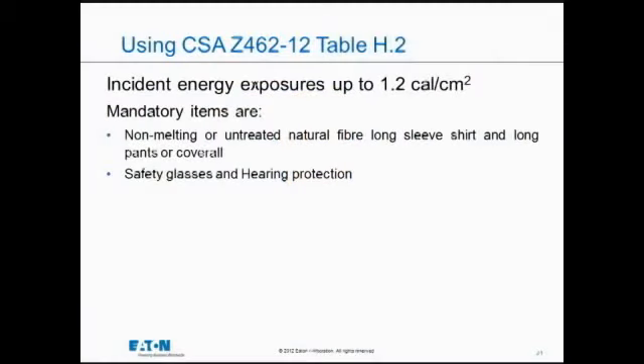They've tested jeans, cotton jeans, 100%. That will ignite somewhere around 2 calories. So there's a fine line between catching on fire and not catching on fire when you're wearing non-melting natural fiber. The only other thing that's required is safety glasses and hearing protection. Protect the eyes from shrapnel, protect the ears from pressure wave. That's up to 1.2 calories.